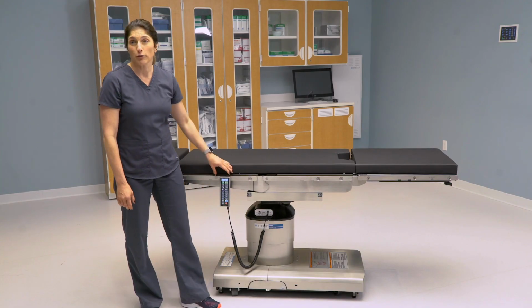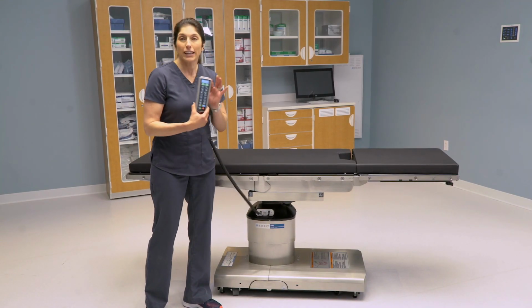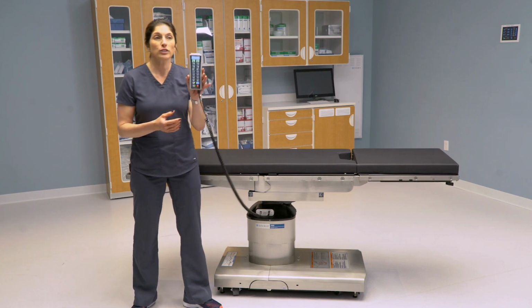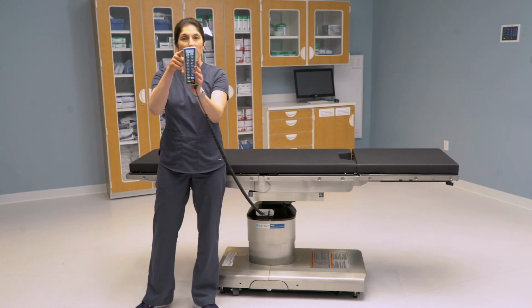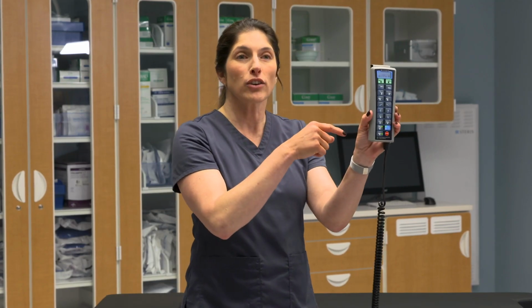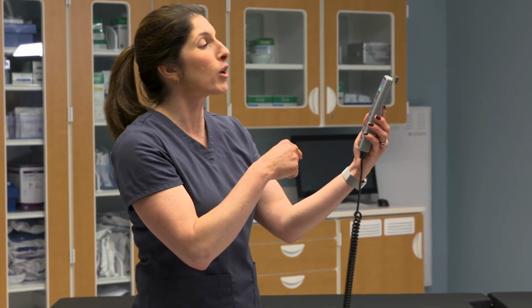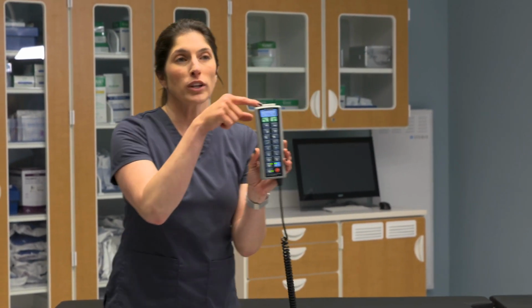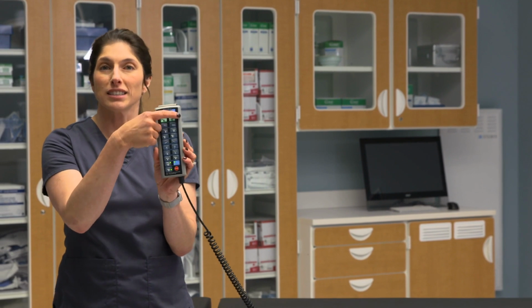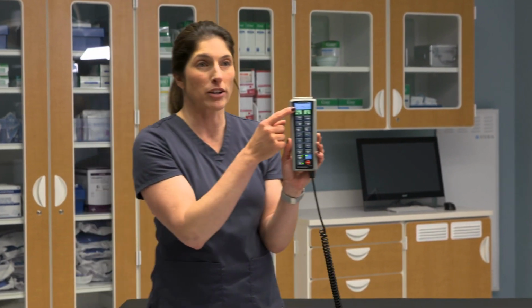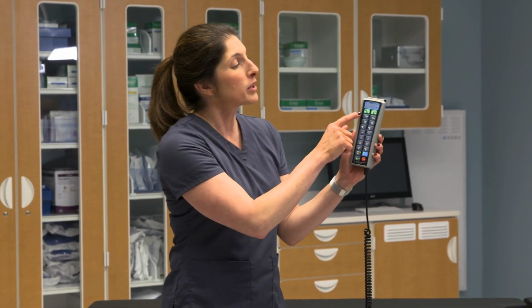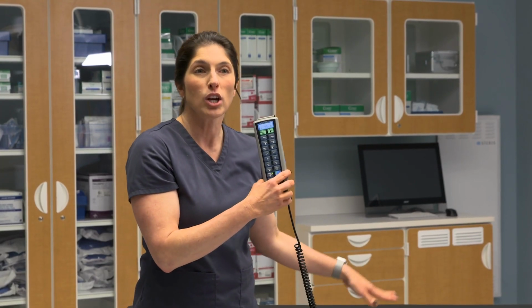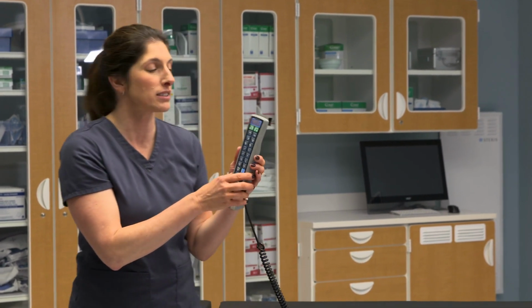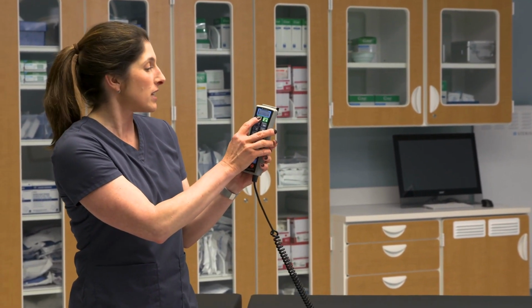So another thing that's different from your 3085 is the hand control on the 4085. The first thing you'll notice is the LCD readout at the top. This is an indicator giving you all sorts of feedback on the smart hand control as to what you're doing, what you're articulating, and the status of the bed, unlock, lock, the battery status, etc. So at the very top, you'll see we've got slide head and slide foot. So as we talked about, you have the ability to slide your tabletop to the head or to the foot for C-arm access. So we can slide to the head.